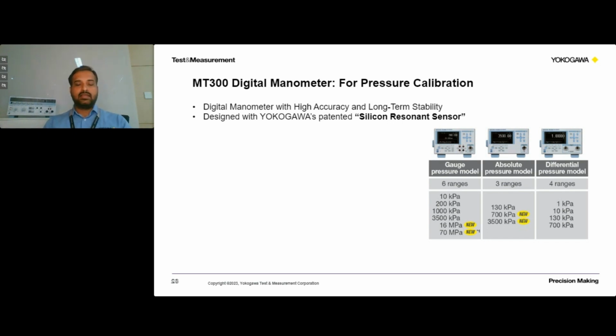unlike piezoelectric sensors where piezo resistance and piezo capacitance are involved. Over a period of time, they are bound to drift, and they are bound to develop errors due to electrical parameters, and because of A to D conversion, they are bound to drift. Whereas this silicon resonance sensor, we call it a drift-free sensor. It will easily run for 5 to 10 years without any drift. Since it is giving a direct frequency output, there is no room for A to D conversion error, and there is no room for errors developed because of electrical parameters. So from that point of view, it is the most stable sensing technology available in the market. So these manometers have this silicon resonance sensor as the pressure sensing element inside.